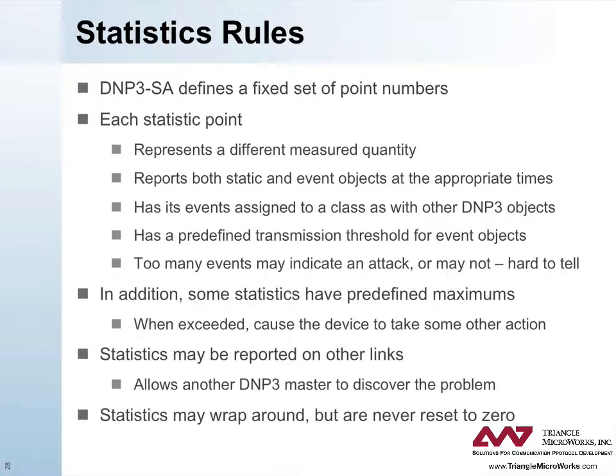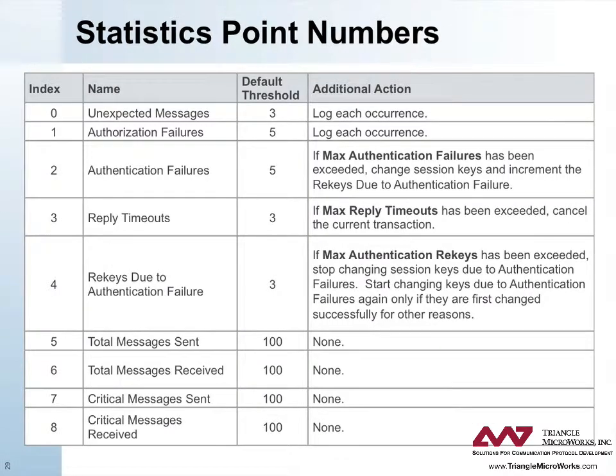Statistic points also have a predefined transmission threshold for event objects because too many events may — but does not necessarily — indicate that an attack is underway. Some statistics have predefined maximums that when exceeded cause the device to take some other action. Statistics may be reported on other links, which allows another DNP3 master to discover the problem. Note that statistics counters may wrap, but they are never reset to zero. This slide and the next provide a list of statistic point numbers along with the default threshold and additional actions that may be taken.